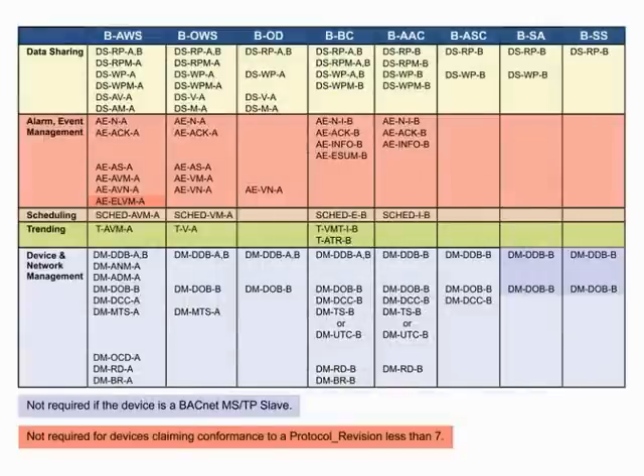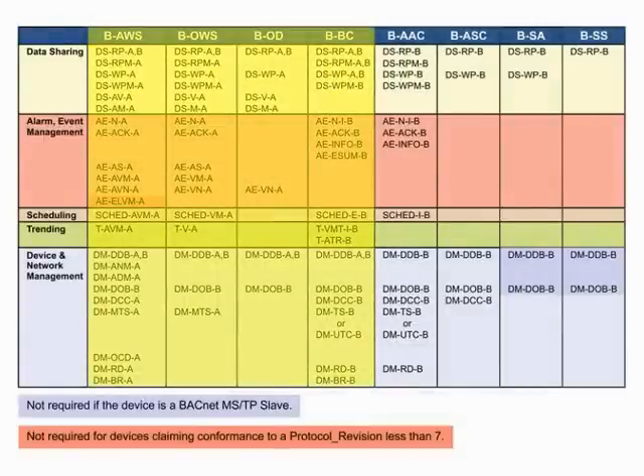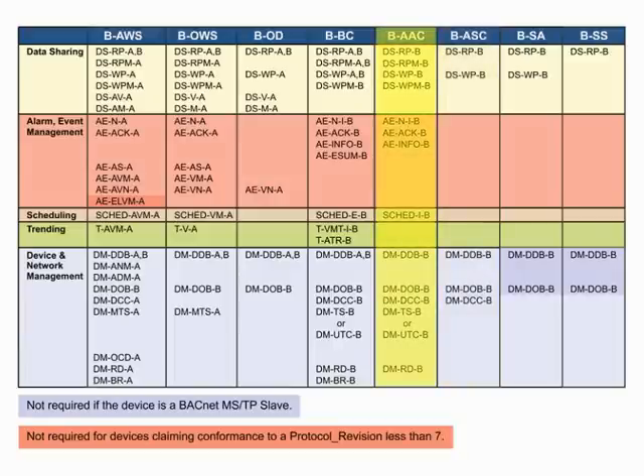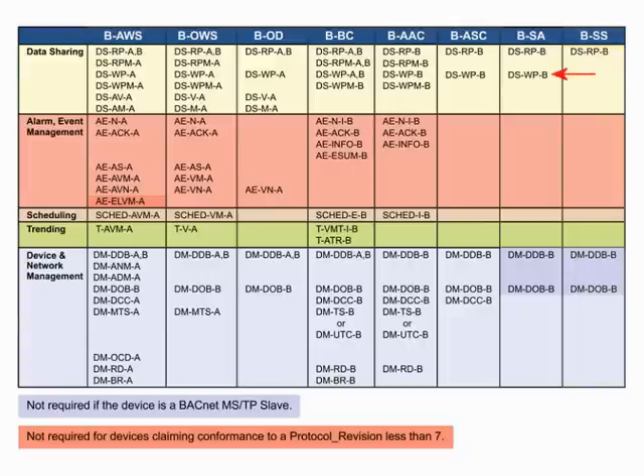Client functionality is found in more sophisticated profiles to the left of the chart. But if you look at the device profile table, you will notice that this device does more than what is called for in a B-ASC device profile, but not enough to make it a B-AAC. Look at the Smart Sensor profile, B-SS, which is the simplest device. It must execute a read property, but not a write property, because it is only a sensor that is read.